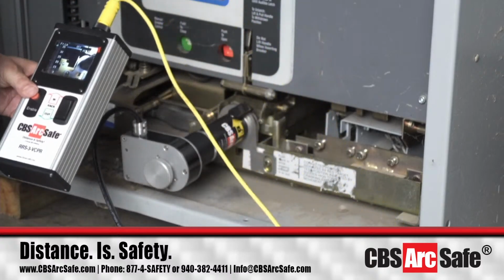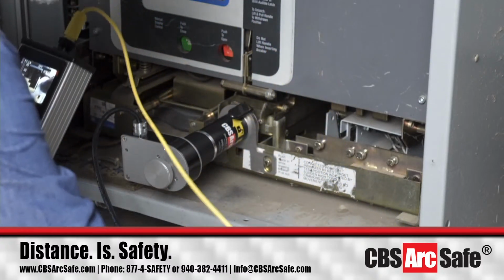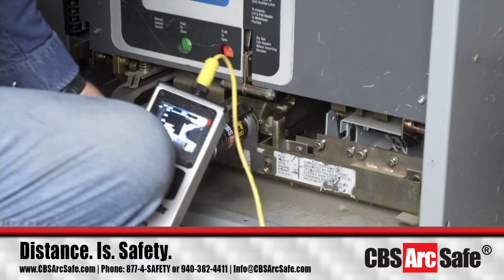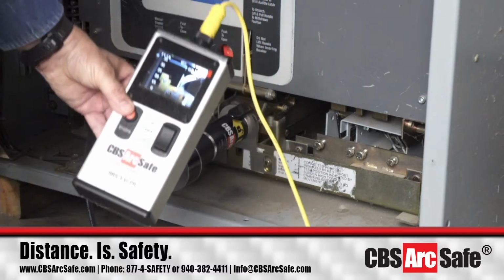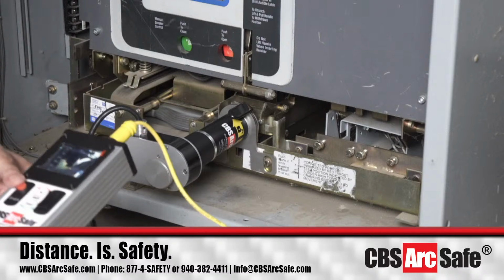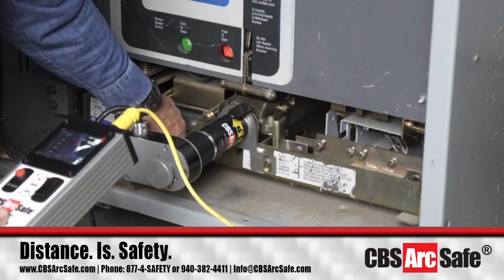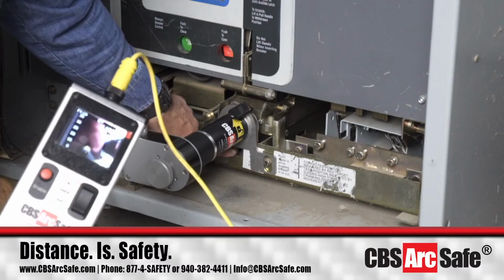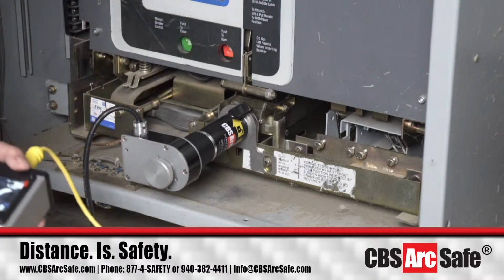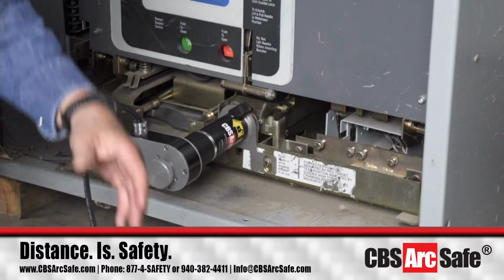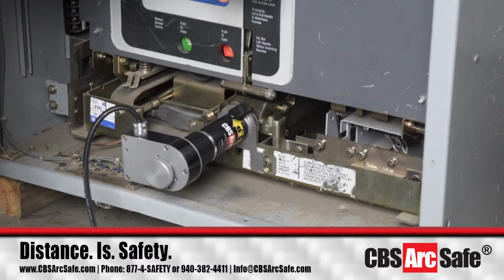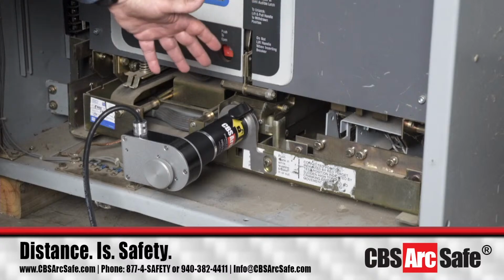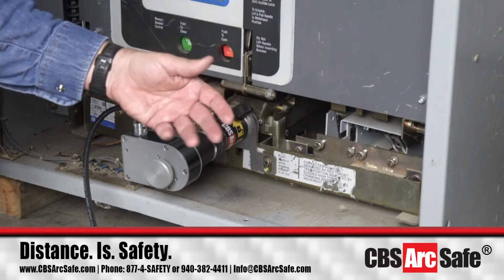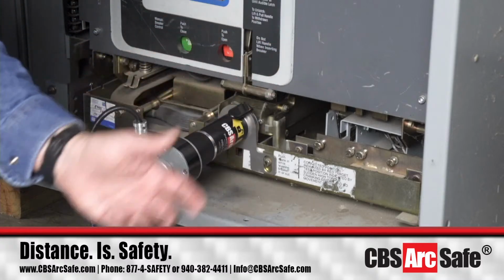And I'm going to hold this over here so hopefully we can see this happen a little bit better. Great. Yep. Don't rack it back. We're good? Okay. So one of the things to note is the indicator does show you down here where the flag is. And there's a little red flag that displays when the breaker gets fully back into the operational position. So that's one of the advantages. It actually does watch to see that that flag comes into display.